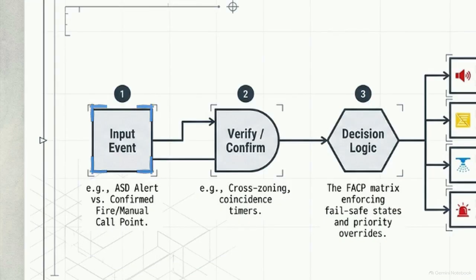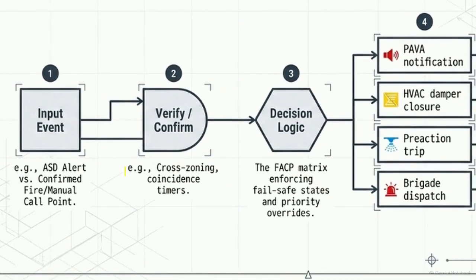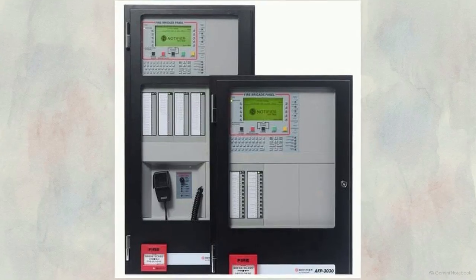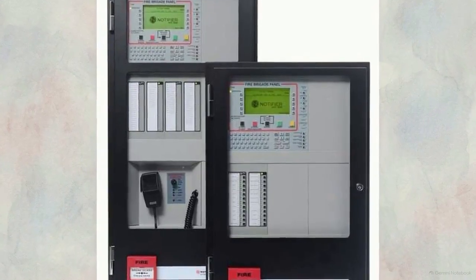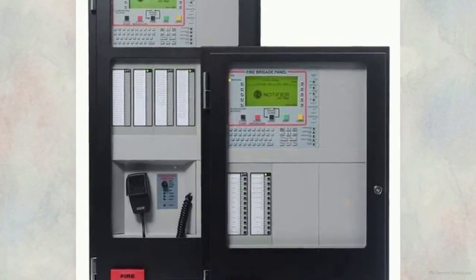A single alert should never trigger suppression. Instead, the signal must pass through a linear deterministic circuit to be verified. The input hits verification gates, such as cross-zoning multiple sensors and coincidence timers, to definitively eliminate false positives. Once verified, the logic falls to the fire alarm control panel, the ultimate source of truth in the facility.